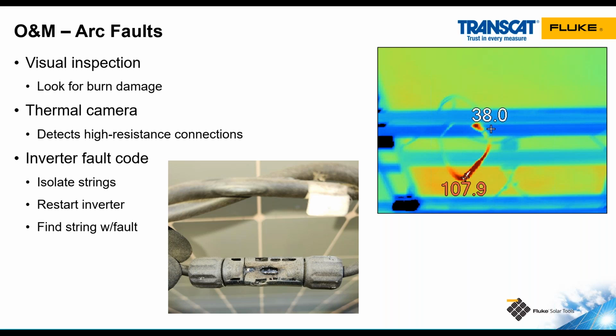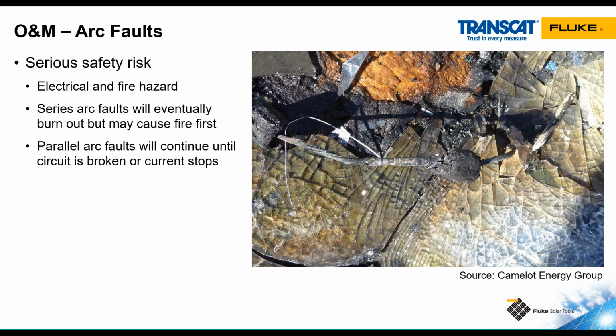Inverters all have arc fault detection in them, and often they will show an error code and shut off, indicating there's an arc fault. You can do a troubleshooting sequence where you separate certain sections of the array, turn the inverter back on, and see if the fault code still remains. If it's gone away, you know the arc fault is in that section of the array. If it's still there, then you need to isolate a different section of the array and continue that workflow until you find the culprit. Arc faults are a safety hazard.